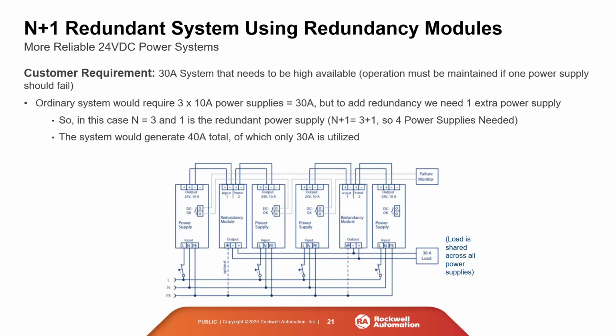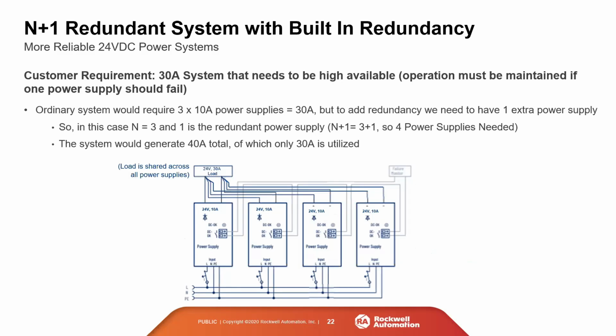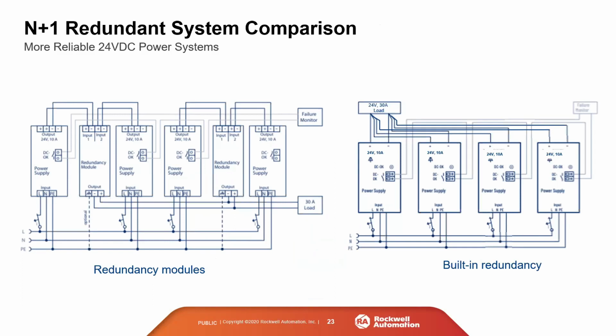This system would generate 40 amps total, but only 30 is going to be utilized. And the cool thing about when you do this is that the load is shared across all power supplies, which increases the life of all of them. So get some extra bang for your buck. We can also build our N+1 with our built-in redundant power supplies. So let's take a look at this. It's the same 30 amp system, but we just need 4 power supplies with the built-in redundancy to get our 3+1. So 3 would be normally required to operate our 30 amp system plus the 1 for our redundancy. If you take a look at both, you can see that the previous redundancy module system required 6 units, and the built-in system only required 4.